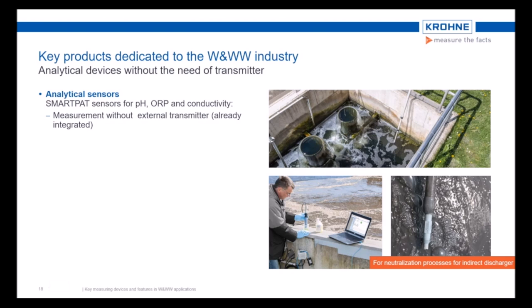This construction also enables the user to calibrate the sensor at any place. All relevant data are stored in the sensor directly. You can calibrate the sensor directly at the installation point, as you can see in the application picture, or even better, do it in the lab, always under the same climatic conditions, which brings you up to a 4 times longer lifetime of the sensor. All SMARTPAT sensors can be installed in already existing infrastructure due to a standardized communication via 4 to 20 milliamps HART.